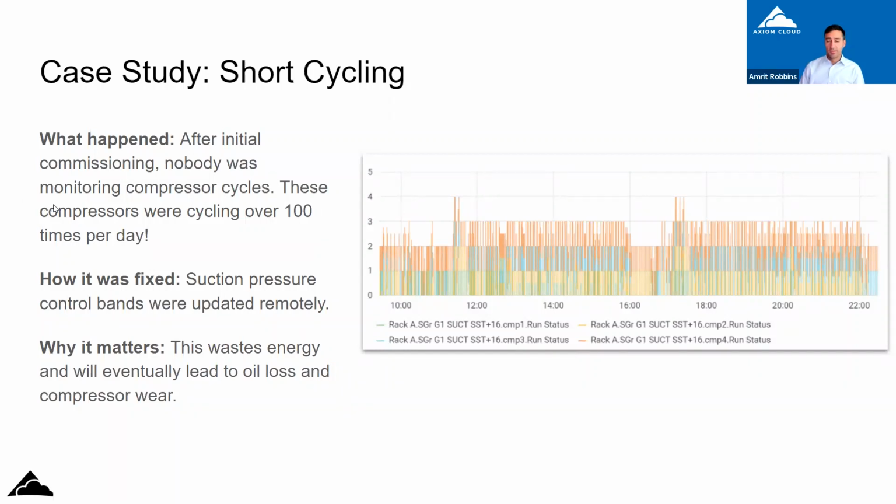So, these are a couple examples of how data, data analytics, and looking at trends in data can be used to identify the root cause of issues that would otherwise kill compressors. Sometimes this could be killing compressors within 24 hours. Other times it might be shortening a lifespan from 15 years to 5 years. But in each case, this is painfully obvious in the data.